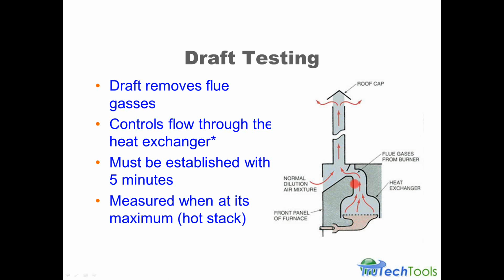We're also looking for the draft to be established within 5 minutes of startup on atmospheric appliances, because that's due to the buoyancy effect of the heat going up the system to create the pull in a natural draft situation. And we want to measure when it's at its maximum. That would be when you have a hot stack or a warm stack, and that buoyancy would have been established.